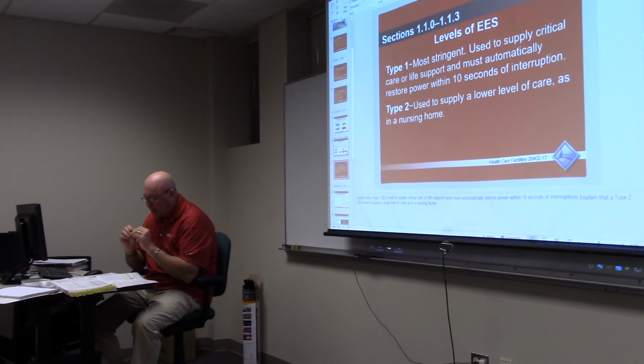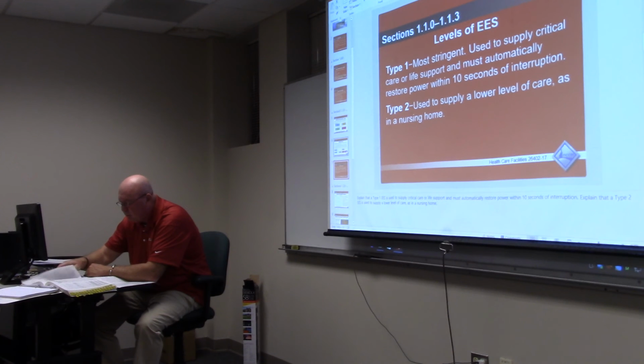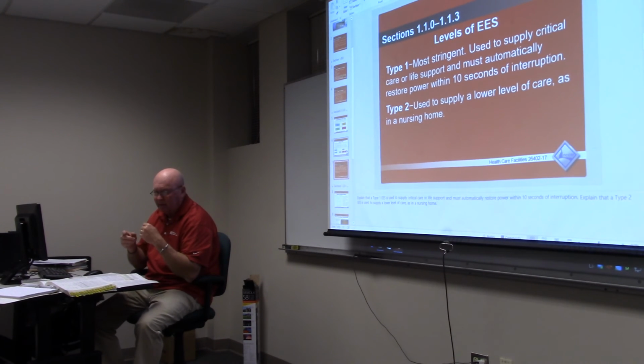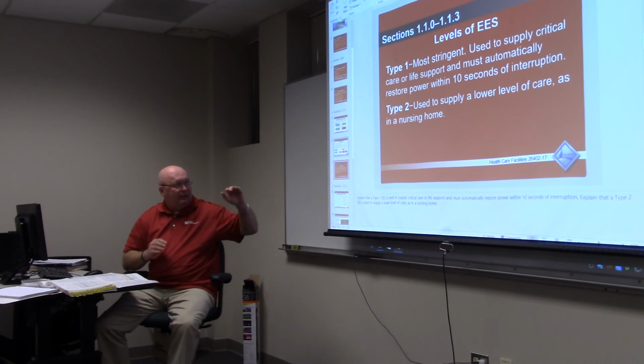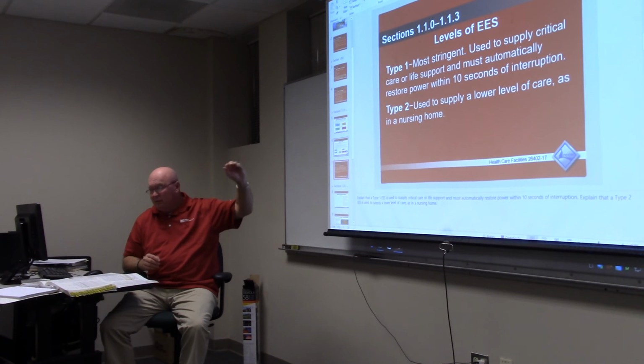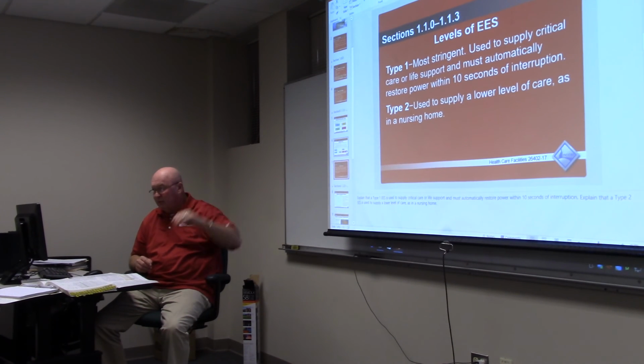These two branch circuits are the life safety branch and equipment branch. The number of transfer switches is based on reliability, and so on. Some of the things it refers us to is 517.42, which talks about automatic connection to a life safety branch, some type of automatic device that switches over and transfers power in case we lose normal power. Type 2 is not as stringent as type 1, but there are still important areas to consider.